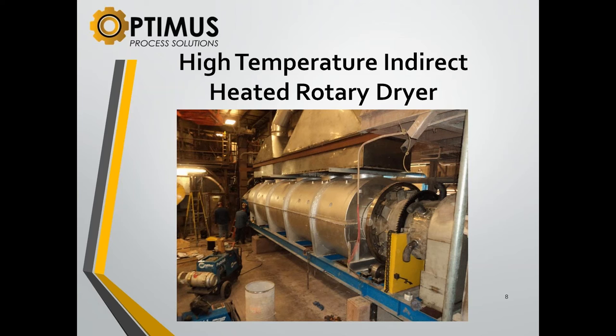A lot of people term this, we call it a high temperature indirect heat dryer. A lot of customers may call it a kiln. Some people may call it a calciner, depending on what's going on inside it. Calcining typically is a term used for driving off molecularly bound water. You might have a product that has a certain free moisture in it, but there also may be water that is chemically bound to the material. That water would actually be in a crystalline format.